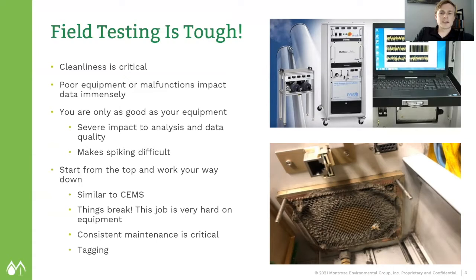You're never going to pass a spike when you have faulty equipment. This is largely based around temperature swings. If your heated lines fail or if they can't get up to calibration temperatures, the FTIR samples hot and fast. That's what we always like to see. There shouldn't be cold spots. The temperatures that you're sampling at should be matching your instrument and the references that you're using. That's one of the big things that we see with other firms out there. We'll get to that in a little bit.